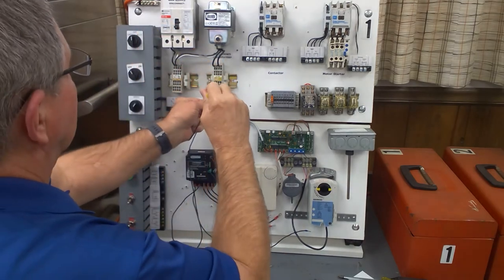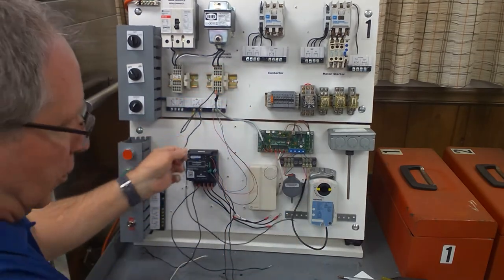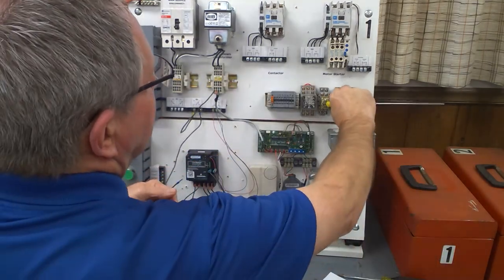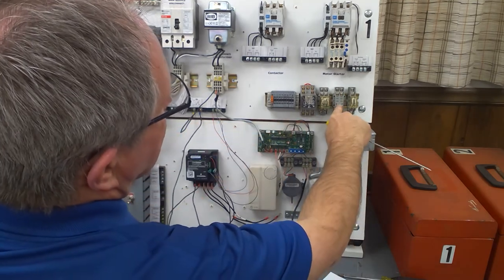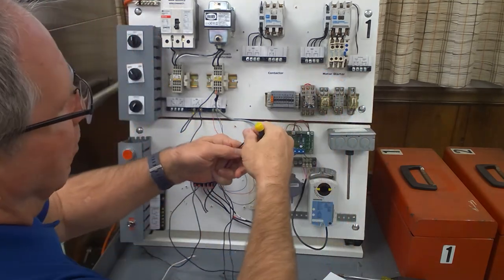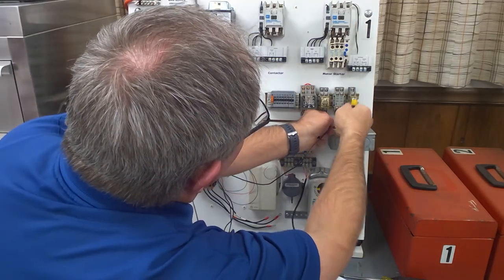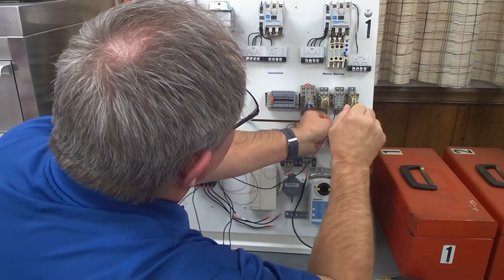I'm going to start with this wire right here, 24 volts to the cooling controller. This is the terminals for this switch. I'm going to take 24 volts here. Off of the switch, I'm going to go over to the coil of the control relay. When you look at these plug-in relays, you can see the vertical blades here versus the horizontal ones on top. The terminals right underneath the vertical blades are going to be the coil.